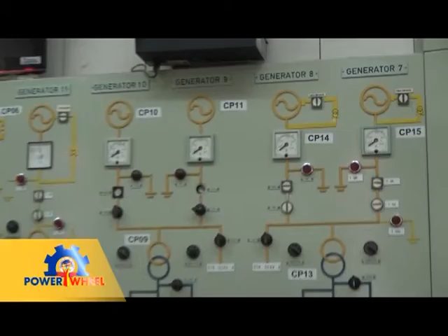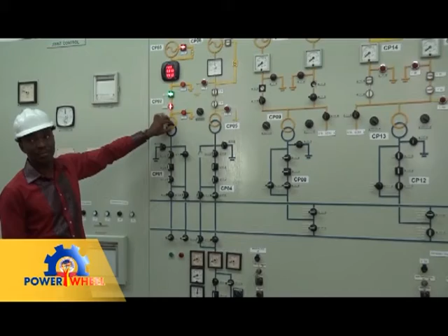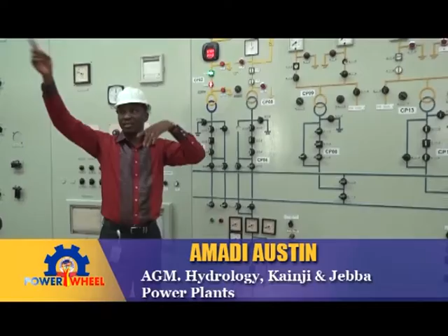All generators operate at the same voltage of 16 kV. It means that with this generator running, 16 kV is produced, and the 16 kV goes out through a breaker and isolator to a transformer. The transformer is a step-up transformer. The transformer will step that 16 kV to 330 kV, and then it goes into the switchyard. Our goal is to generate electricity in bulk that we send out. So it will be transmitted over long lines to areas, small towns and villages where this is needed. For us to be able to transmit to far places, we have to raise the voltage high so as to reduce losses on the line and to reduce the cost of the transmission. So that is why the 16 kV from the generator is stepped up to 330 kV. And you can see here, yellow shows 16 kV, blue shows 330 kV.